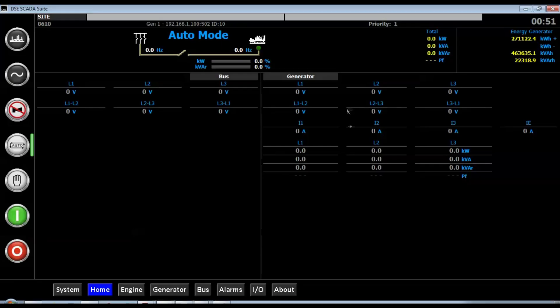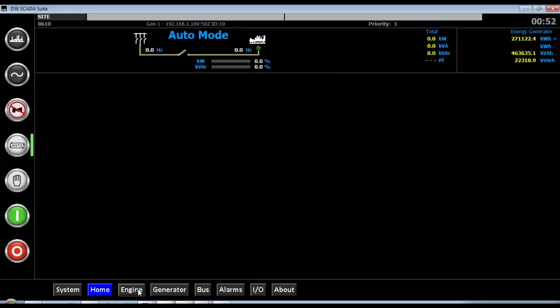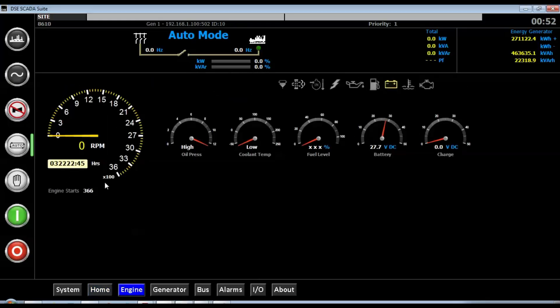From SCADA, you can monitor generator status including voltage, current, power, and power factor. Engine details include running hours, starts, battery voltage, oil pressure, and water temperature. You can also view energy counters, bus values, active alarms, inputs and outputs, and controller details such as software version and bootloader.